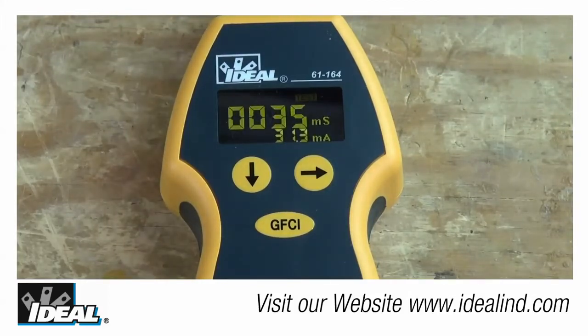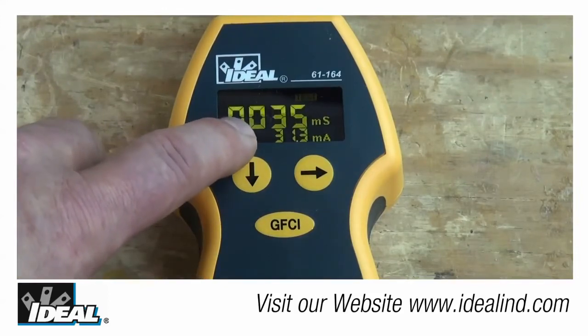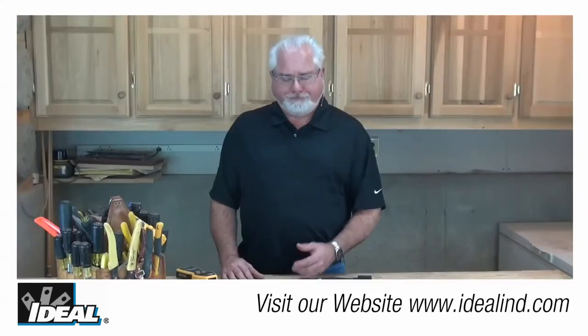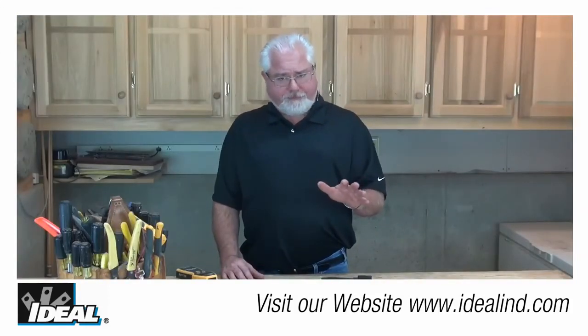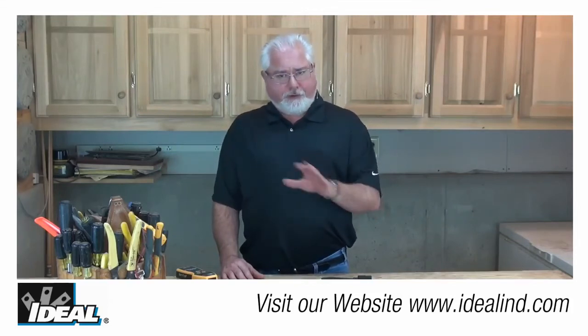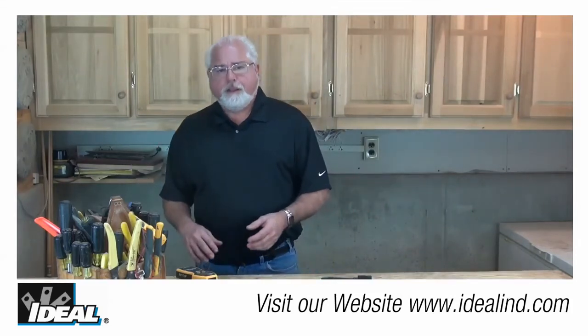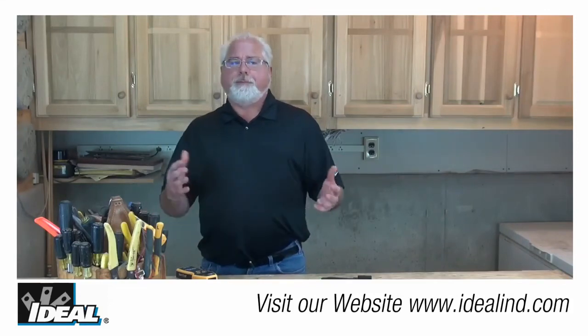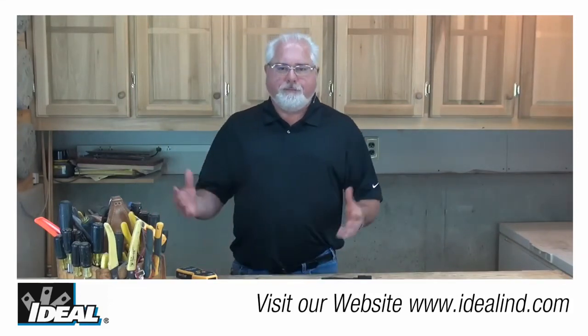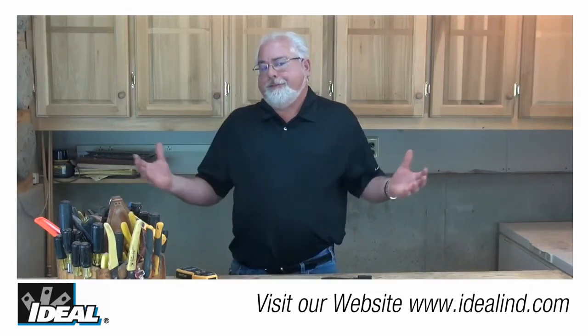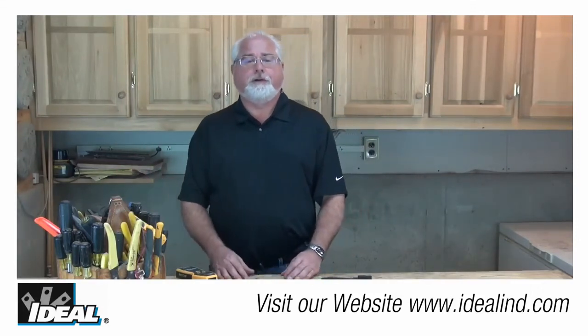And if the equipment protection device trips, the display will blank out with the loss of power. Now, when the equipment protection device is reset and power is restored, the unit's going to display the actual trip time the device took to respond to that current imbalance and then open the circuit for you. Now, again, if the equipment protection device fails to trip, the tester is going to terminate that test after 6.5 seconds. And then further inspection should determine whether that equipment protection device is faulty, maybe it's not installed properly, or again, if there is any circuit protection on that circuit itself.